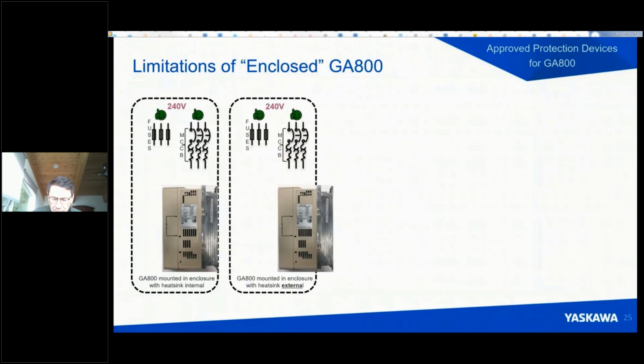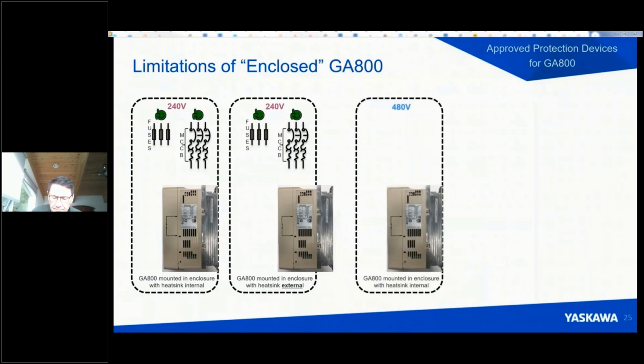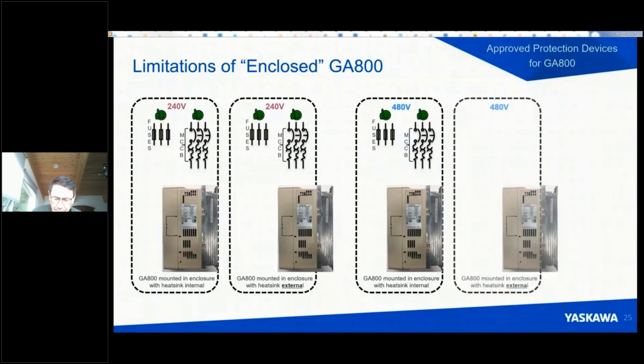And for the 240 volts, even when the heatsink and capacitors are on the backside, this is no problem for the 240 volt drive. If you think back to the prior explanation of those failure modes, remember that when we short the capacitor on the 240 volt drive, nothing bad happens. But when we move on to 480 volt, again, with the drive mounted completely inside of the enclosure, either fuses or a circuit breaker is absolutely acceptable.